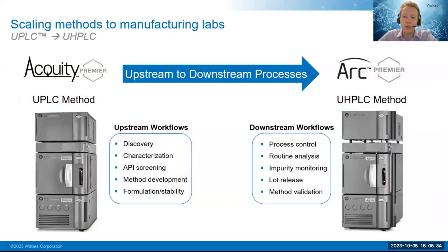For the workflows we'll be going over today, we will be transferring methods from the Acquity Premier system to the Arc Premier system. And for some of the listed upstream workflows, LCs are engineered to provide the highest sensitivity through smaller column particle sizes, which are usually less than 2 microns, and smaller tube and column inner diameters, and capabilities to operate at higher pressures.